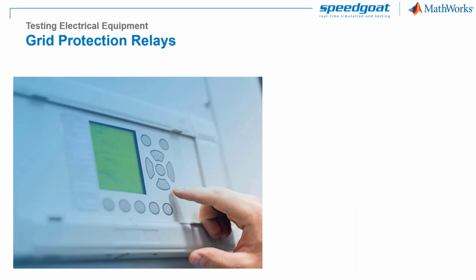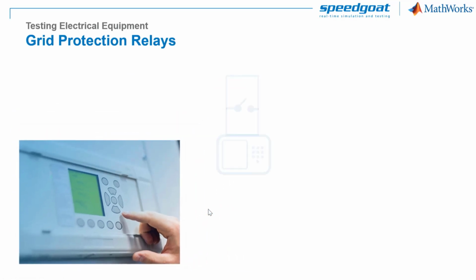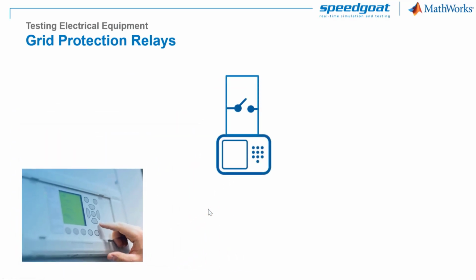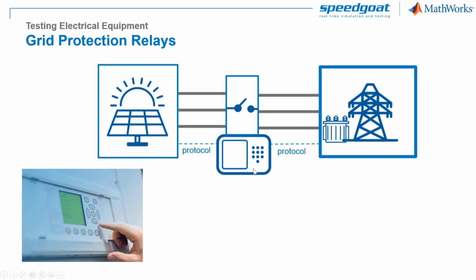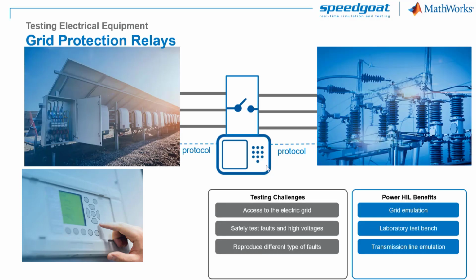When testing relays protecting the grid, systems whose failure could lead to severe damage to the electrical infrastructure, we could carry out low-level tests at extra low voltages in some cases, but testing the complete relay for different grid conditions requires including its current transformers, voltage transducers, and other sensors. Proper testing would require the reproduction of fault currents and voltages for different grid types.